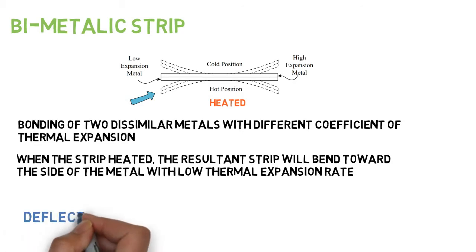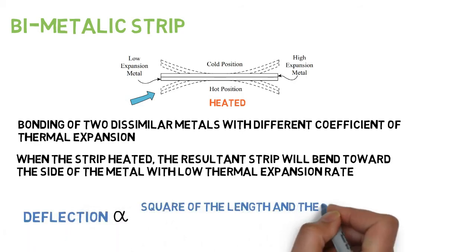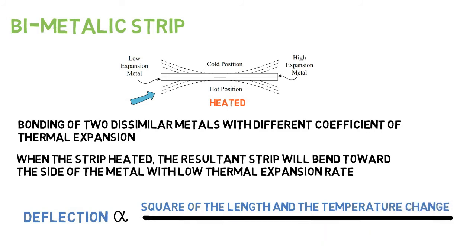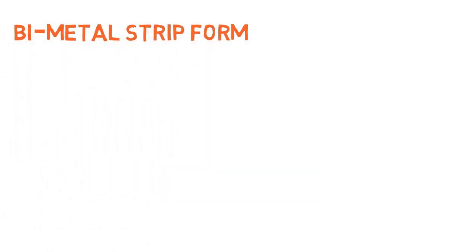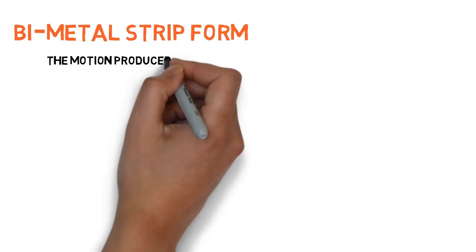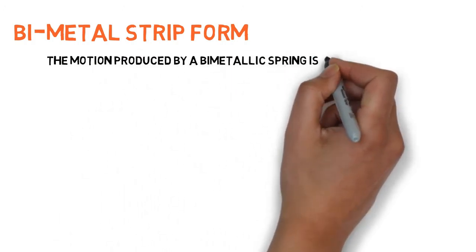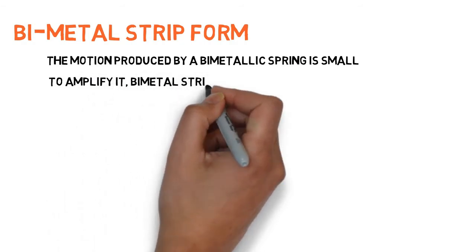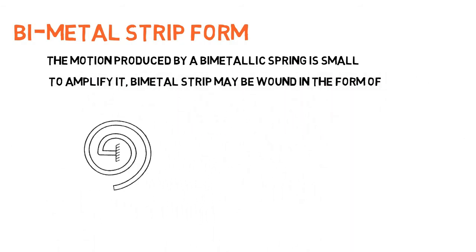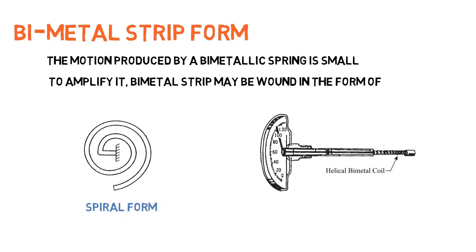Deflection is proportional to the square of the length and the temperature change, and inversely proportional to the thickness. The motion produced by a bimetallic spring is small. To amplify it in a reasonably sized space, the bimetallic strip may be wound in the form of a spiral or a helix.